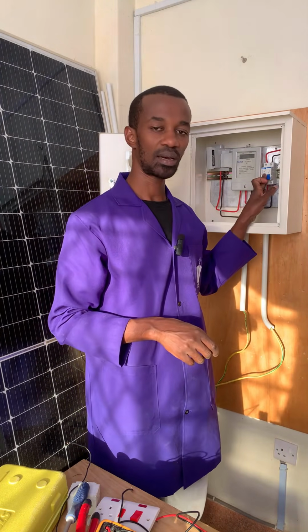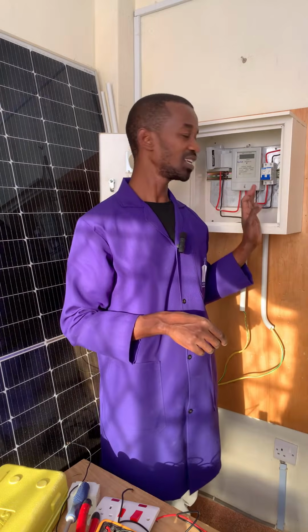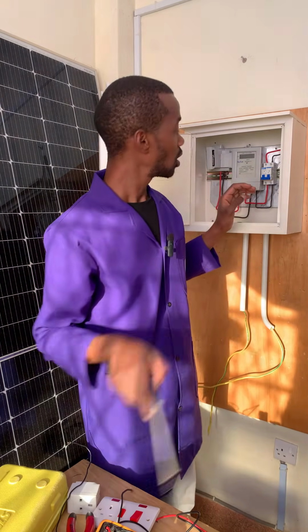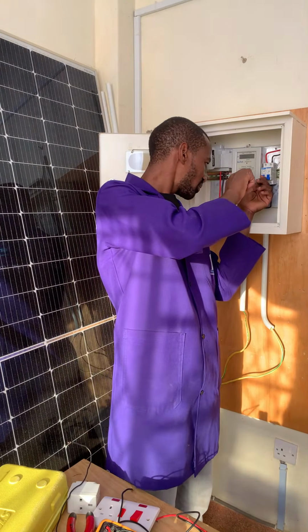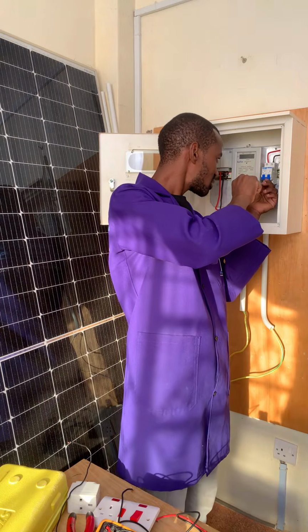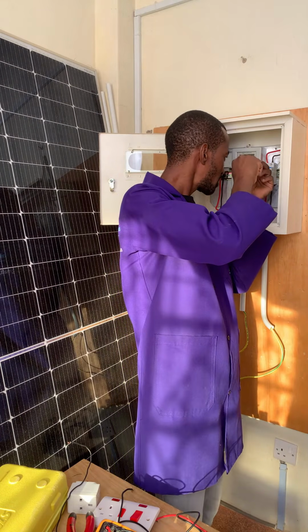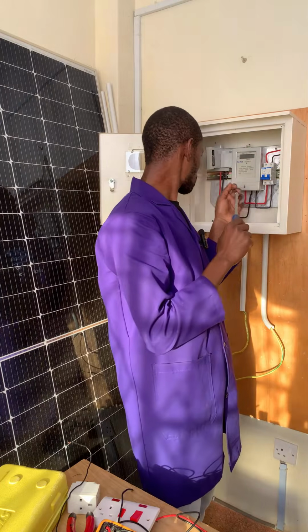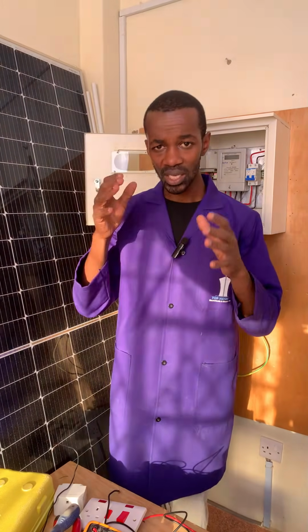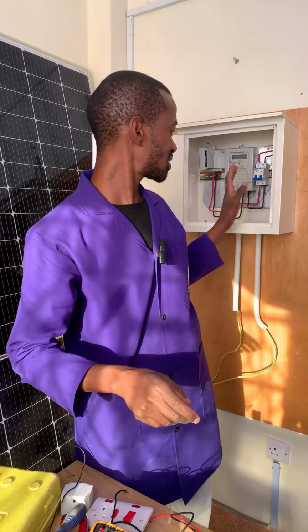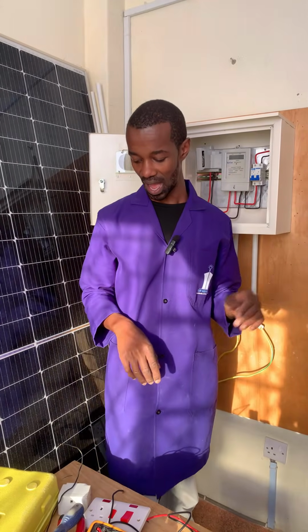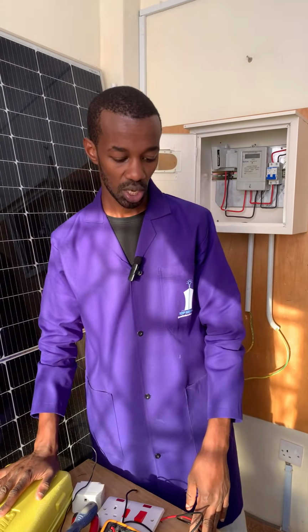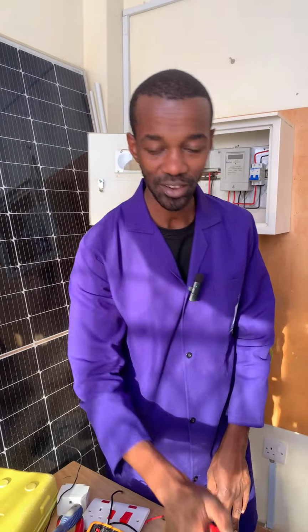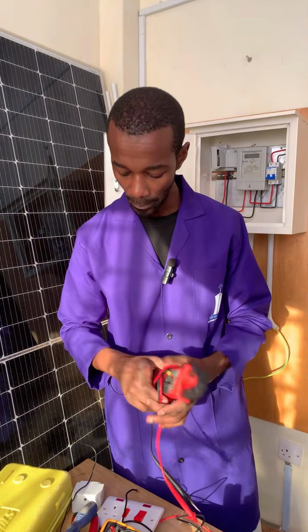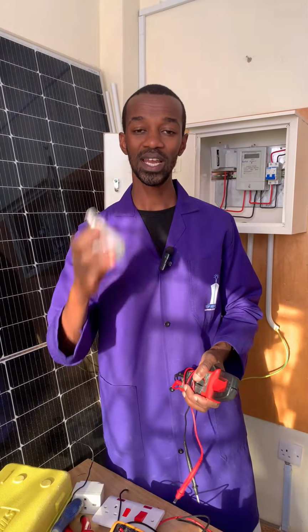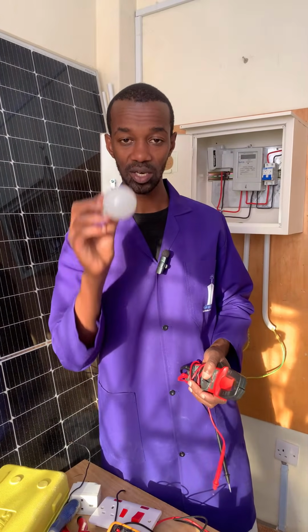If there is a double pole in the meter box, if there are any loose connections, ensure that you tighten all the connections. For instance, here I can see that there are some loose terminations. I don't know which student was doing that. Ensure that everything is tightened. Once it is tight, then check in the customer's house. You must be able to confirm that indeed everything is working properly. The bulbs are not dimming. When the heavy loads are turned on, they are not affecting the lights.